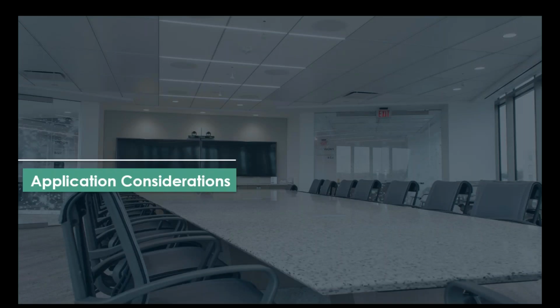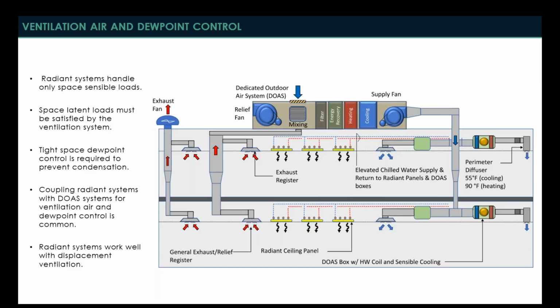So, application considerations. I want to touch on a few things that are very important to the design of these systems that may not pertain to the systems themselves. Probably the most important is your ventilation, air, and dew point control system. More often than not, when we are looking at radiant panel applications or even radiant floor applications, we are going to couple that with a dedicated outside air, or DOAS, system. And the DOAS system is going to handle 100% of the latent load. And it's important to remember for these types of radiant systems that the radiant system is only going to handle the space sensible loads. It is not doing any latent cooling whatsoever.